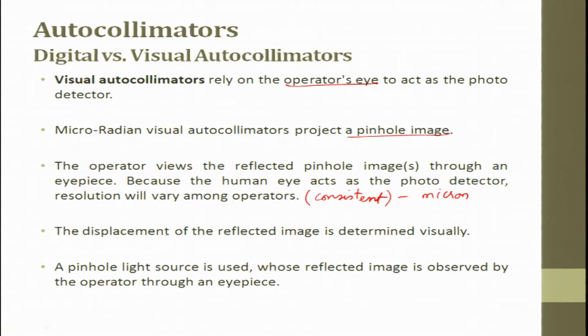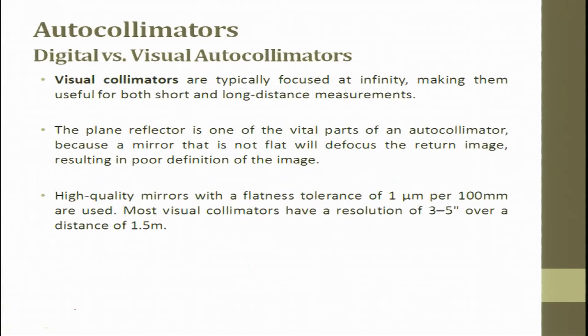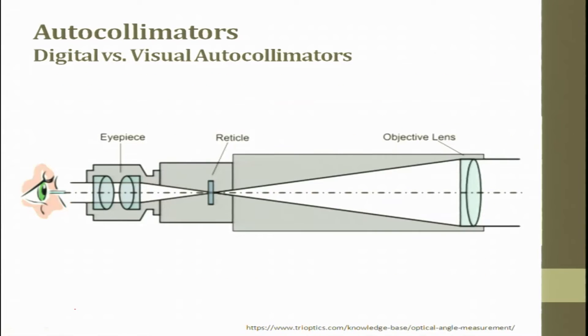The displacement of the reflected image is determined visually. A pinhole light source is used whose reflected image is observed by the operator through the eyepiece. So it depends more on the operator's eye and their judgment.